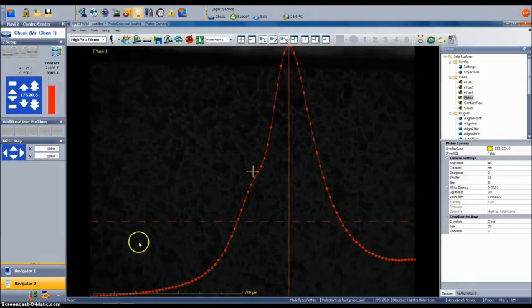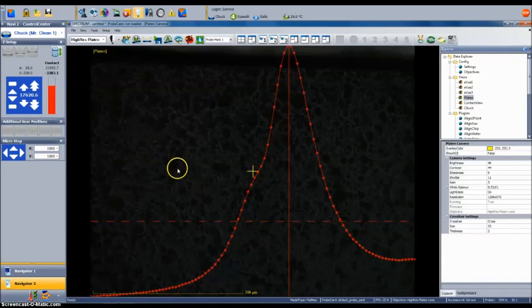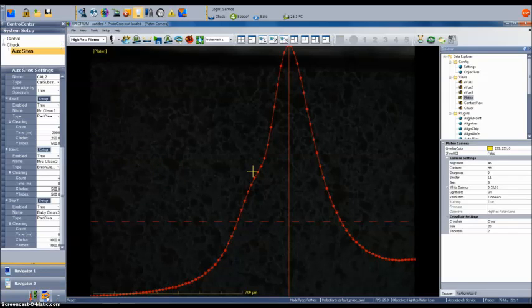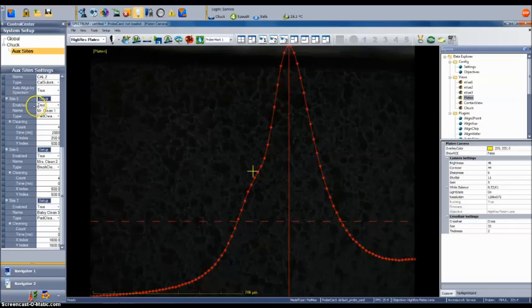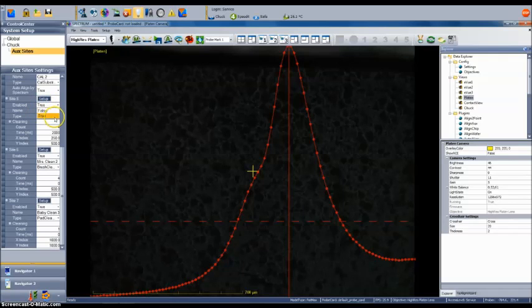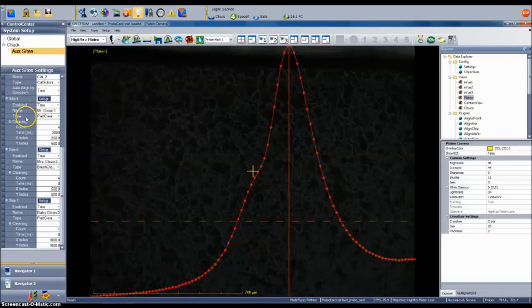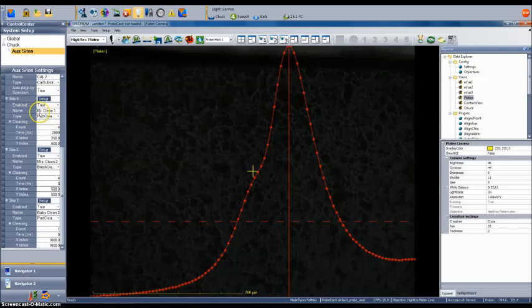With the aux site setup wizard completed, let's take a look at the other controls for probe tip cleaning that are available to the user. Here we have just finished the setup wizard and are focused on the pad surface. Within control center, select system setup, chuck, aux sites, and then scroll down to find aux site 5. Here you can see that aux site 5 is enabled and ready to use. The user defined name for this site is MrClean1 and the type of aux site is a pad cleaner.